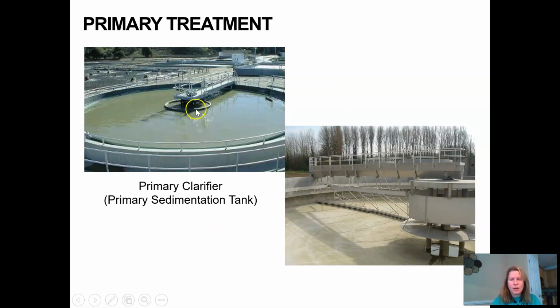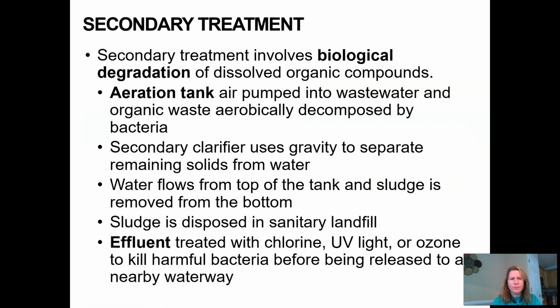Here's an example of a primary clarifier. Here it is where it's empty. There's a bridge here, and then there's a scraper along the bottom. So a person can walk out here. That scraper runs along the bottom, and this arm moves slowly all the time. So here's an example whenever we've got it full of water. The solids are going to settle out along the bottom. The scraper comes along and scrapes the solids, sends them into a pit here where they can be collected. This flows out and they can be collected and carted off to a landfill.